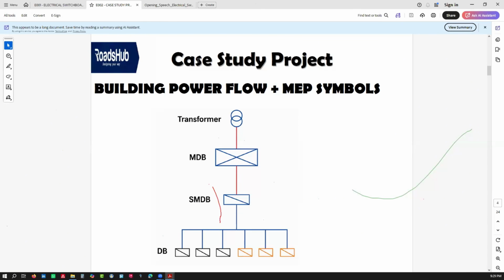The key thing is you need to know how to interpret IEC symbols, or whatever standard you're using, because we are represented from other countries. If you're using NEC or NFPA, what is your symbol for a transformer? For IEC, it's just two rings having an intersection. You have MDBs, SMDBs, and DBs. You need to know these representations so that if you're interpreting that circuit, it becomes clearly understood, and everyone who works on it has a standard way of understanding your design and thought process.